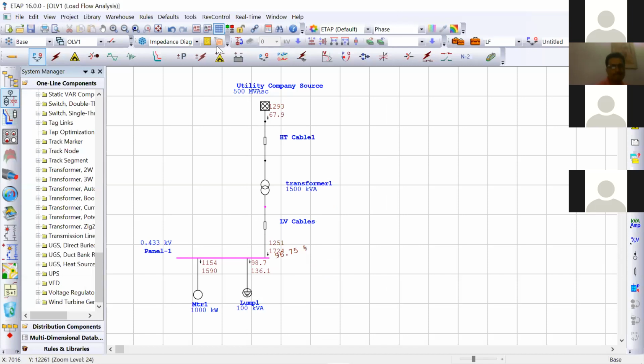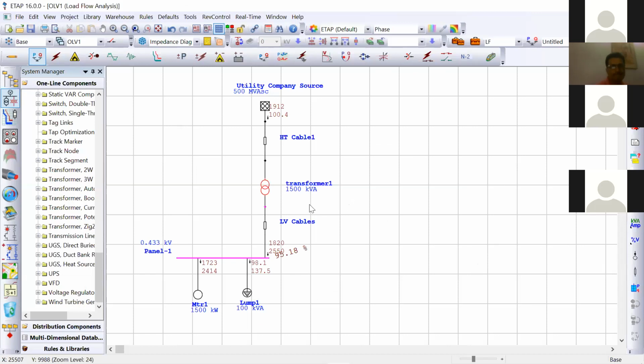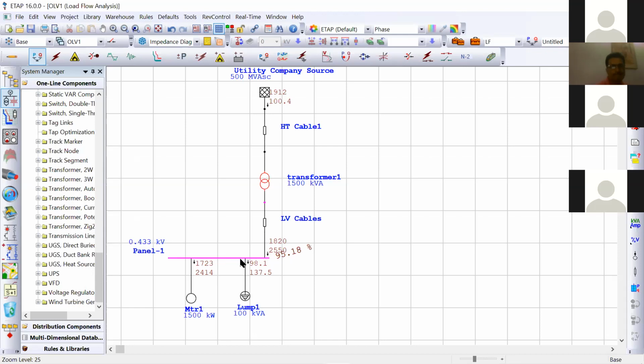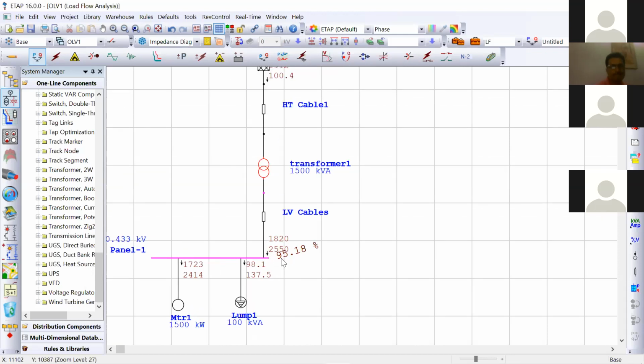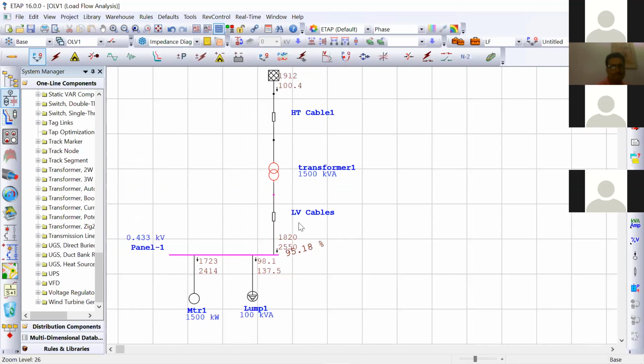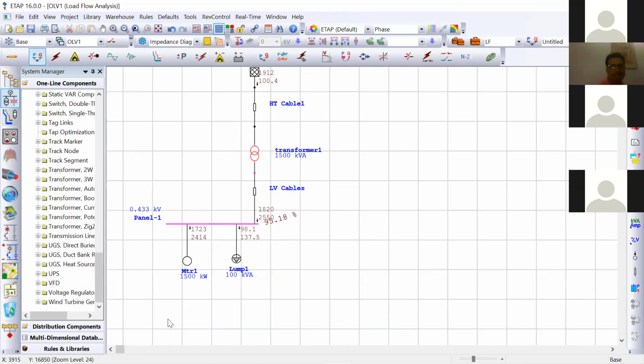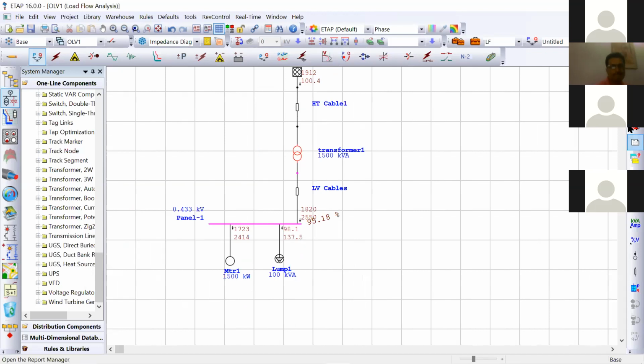Again, if I change this load to say 1500, I'm overloading the system. If I perform this, then it will show me an alarm. Here you can see bus bar voltage level is 95.18%, which was earlier 98%. Also we have to check alarms. Presently there is no such alarm. Yes.